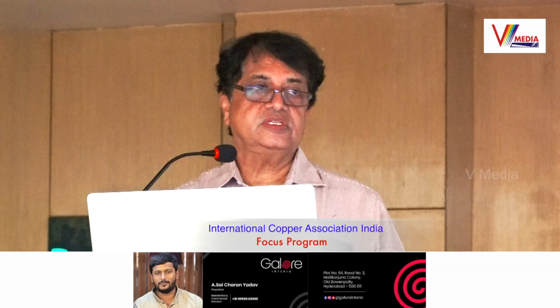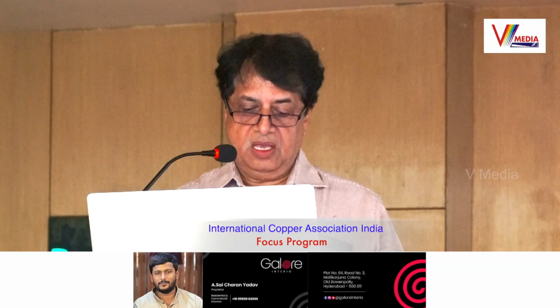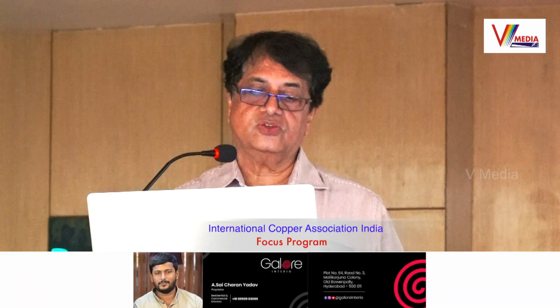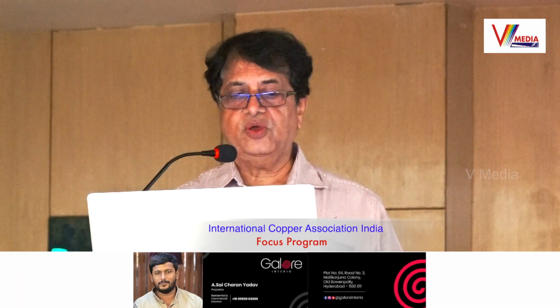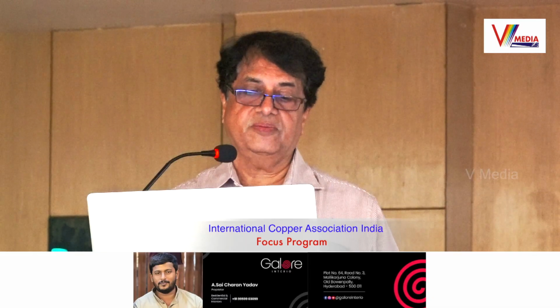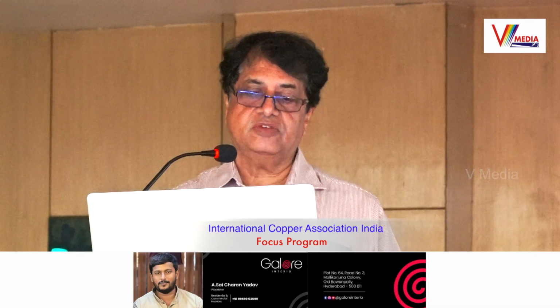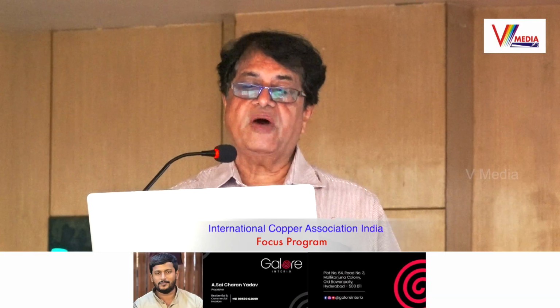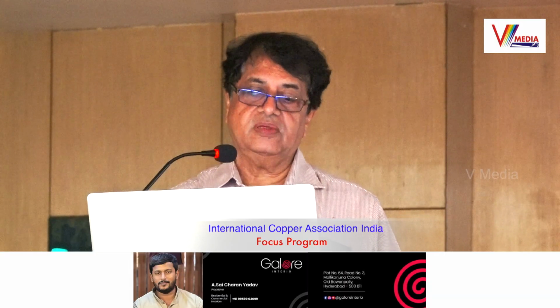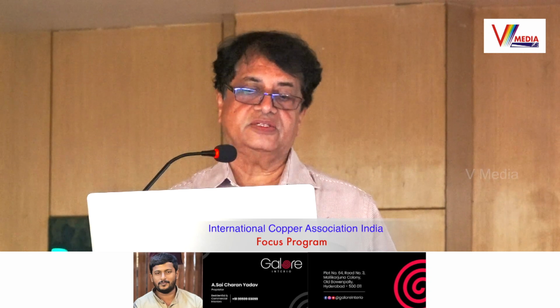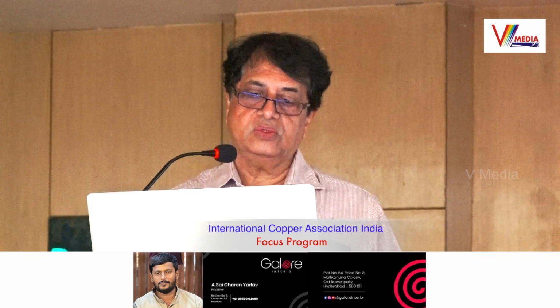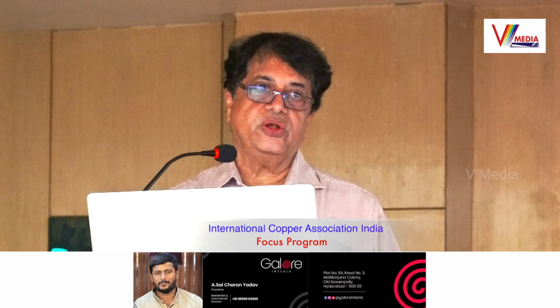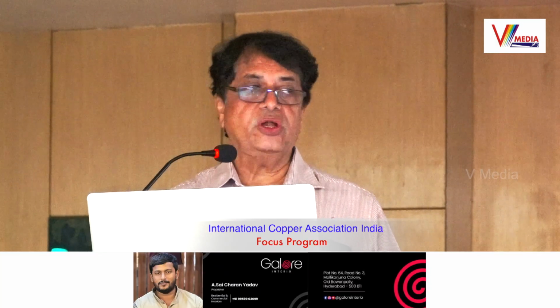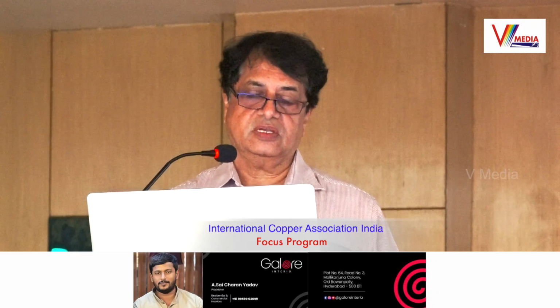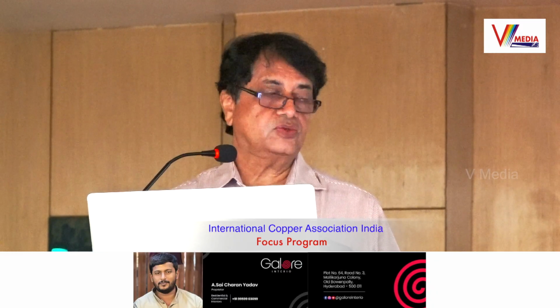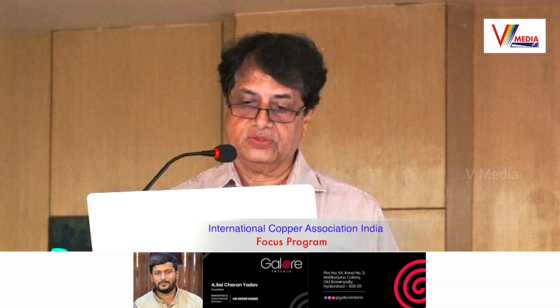One more important thing from the perspective of electrical fire is the switch which is mandatory to be installed. That is called the fire switch. That fire switch is required to be operated when a fire is initiated in the building. The fireman switches off this switch so that the fire may not spread within the building. But for that, one bypass is required for the critical services. This diagram shows how the circuit should be designed, and its location should be at the point of supply, where the service cable enters. There should be sufficient space to install this fire switch also.